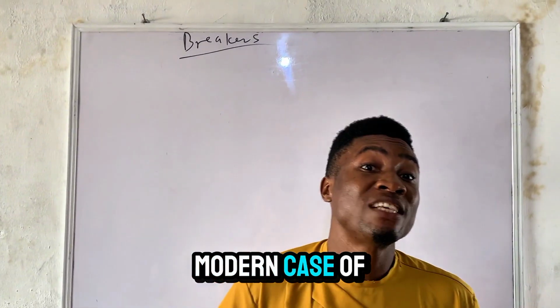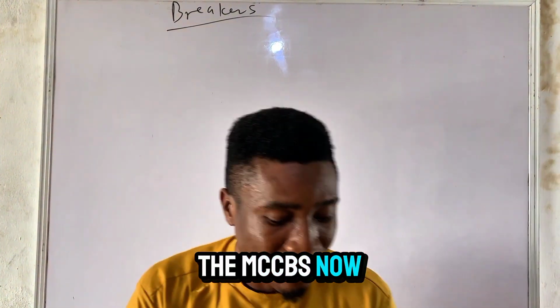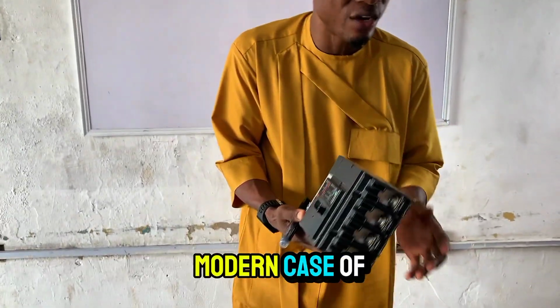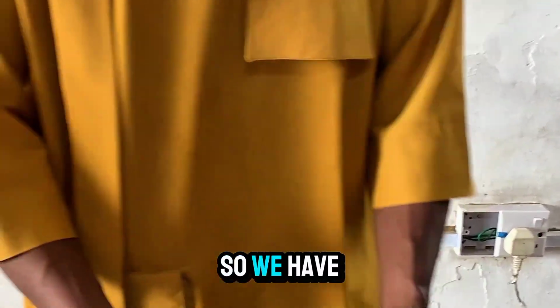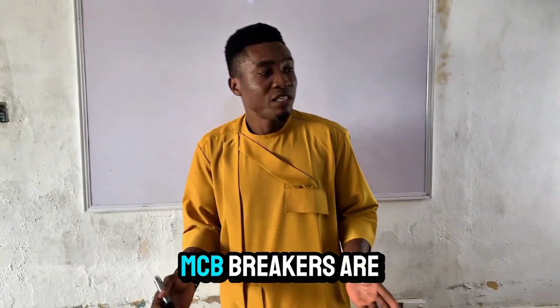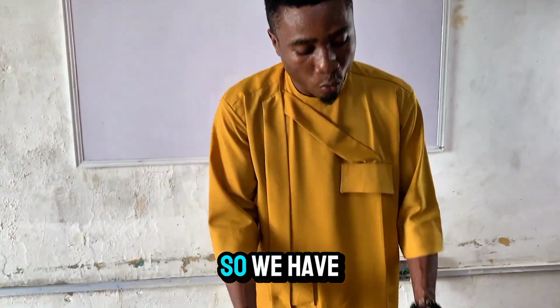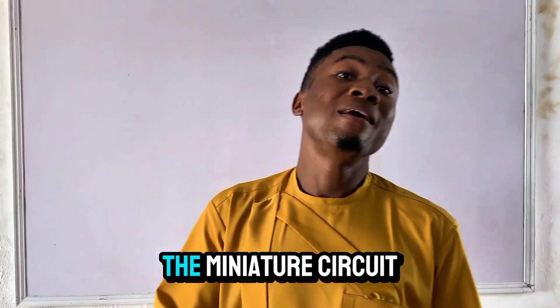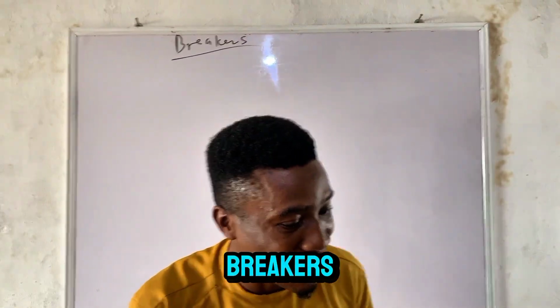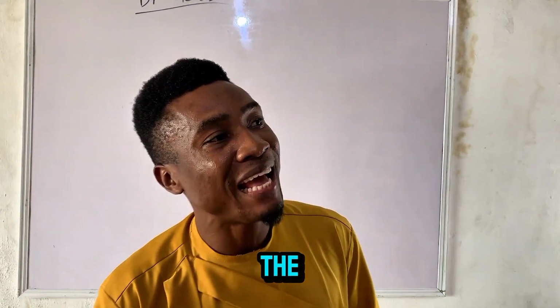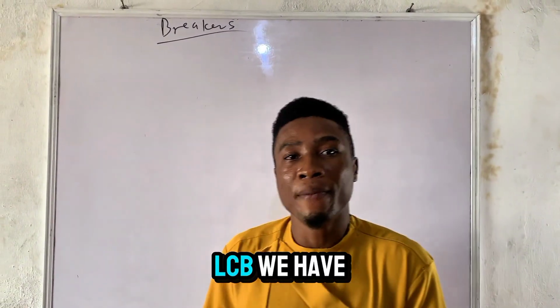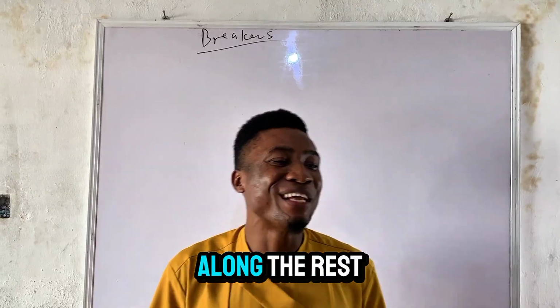We have different kinds of breakers in the market. We have what we call the molded case circuit breakers, the MCCBs. These are MCCBs, molded case circuit breakers, rated in amps. We have what we call MCB breakers - these are small breakers, called miniature circuit breakers, some people call it miniaturized circuit breakers. We also have the earth leakage circuit breaker, ELCB, and we have air circuit breakers and all the rest of them.